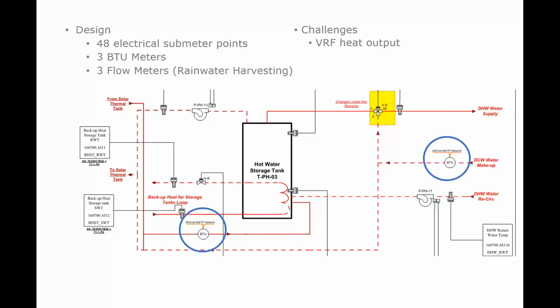Daikin actually worked with the college to develop proprietary software where they could simulate to a very close degree how much thermal energy was running between the compressor and the various fan coils. That was kind of interesting, so that information could be gathered. But there's all sorts of other things - in the design there were 48 electrical submeters, some heat flow meters, and water meters. But syncing those values up to the VRF heat output was a challenge that had to be worked out.